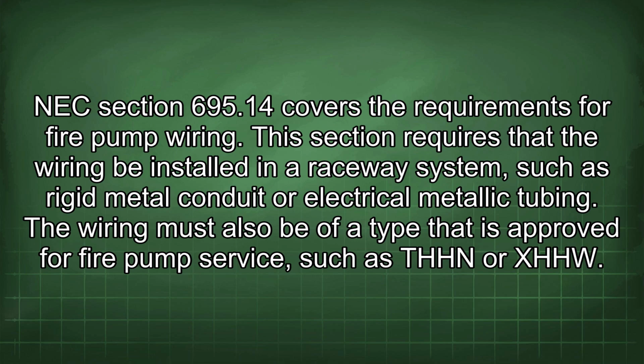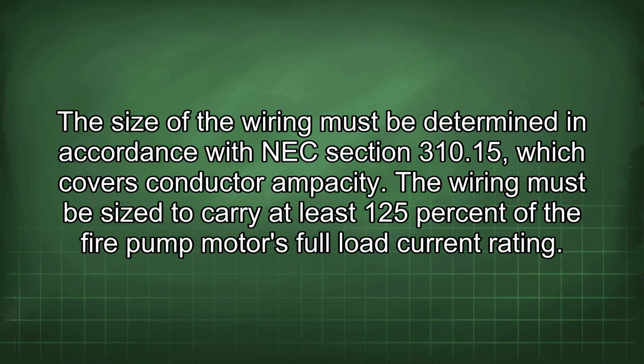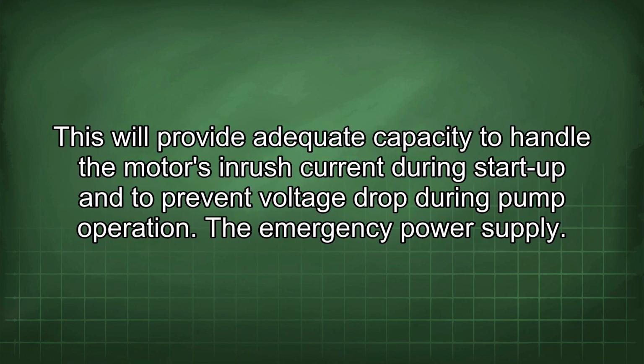This section requires that the wiring be installed in a raceway system, such as rigid metal conduit or electrical metallic tubing. The wiring must also be of a type that is approved for fire pump service, such as THHN or XHHW. The size of the wiring must be determined in accordance with NEC section 310.15, which covers conductor ampacity. The wiring must be sized to carry at least 125% of the fire pump motor's full load current rating. This will provide adequate capacity to handle the motor's inrush current during start-up and to prevent voltage drop during pump operation.